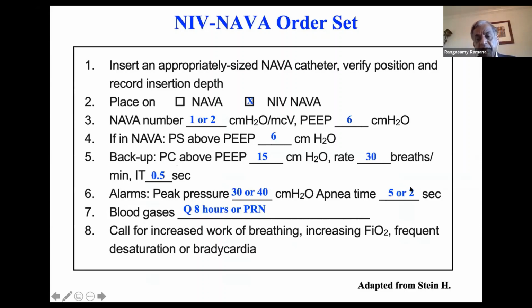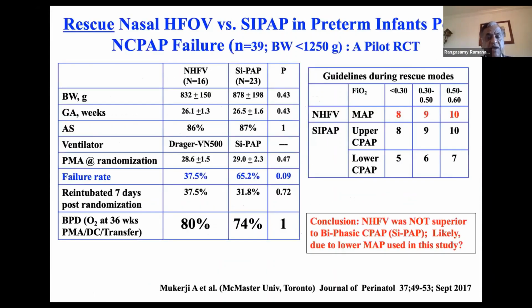Apnea time, you can set it at 2 seconds, which means a rate of 30. If you set 5 seconds apnea time, the rate will be 12. So we normally recommend starting at 2-second apnea time. Blood gases every 8 hours or PRN. Just a sample that Dr. Stein has given. So that's about NAVA.